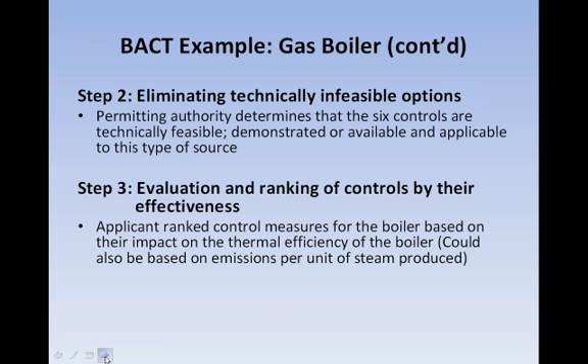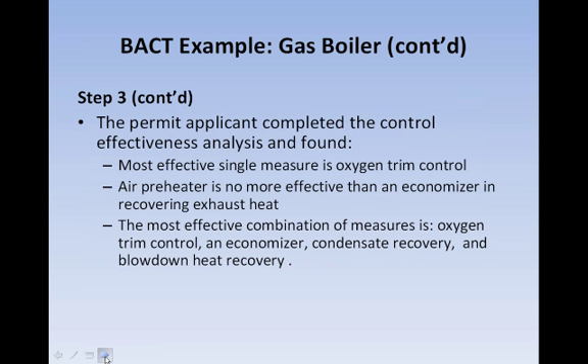The applicant ranked control measures for the boiler based on their impact on thermal efficiency of the boiler after finding that the thermal efficiency was a useful indicator of CO2 control efficiency. So continuing still in step 3, the permit applicant completed a control effectiveness analysis with the following results. The most effective single measure is oxygen trim control. An air preheater is no more effective than an economizer in recovering the exhaust heat, and the applicant narrowed the review to the economizer only.